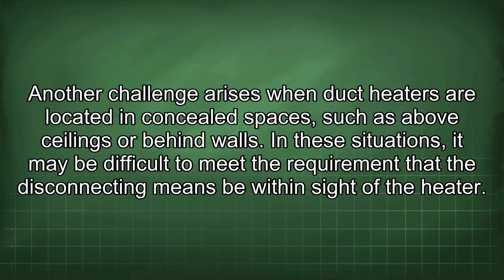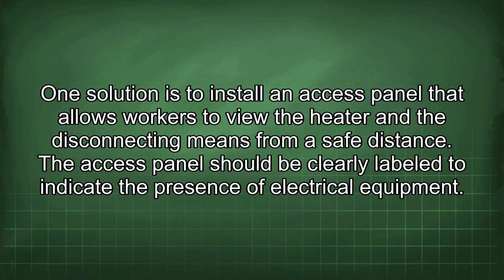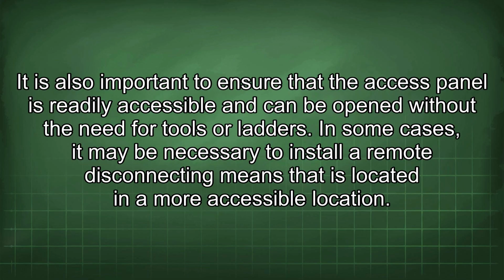Another challenge arises when duct heaters are located in concealed spaces, such as above ceilings or behind walls. In these situations, it may be difficult to meet the requirement that the disconnecting means be within sight of the heater. One solution is to install an access panel that allows workers to view the heater and the disconnecting means from a safe distance. The access panel should be clearly labeled to indicate the presence of electrical equipment. It is also important to ensure that the access panel is readily accessible and can be opened without the need for tools or ladders. In some cases, it may be necessary to install a remote disconnecting means that is located in a more accessible location.